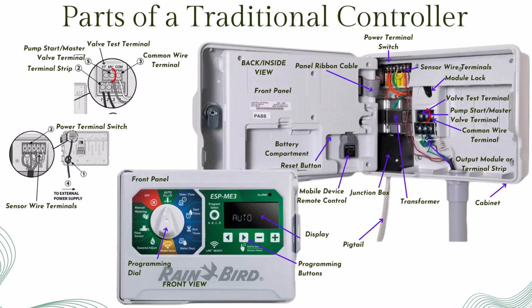The pump start or master valve terminal activates a pump or master valve whenever irrigation starts. Some controllers have a valve test terminal that gives constant low voltage power for troubleshooting valves. The common terminal is the shared return path for all your valve wires. The output module or terminal strip is where each zone wire connects. Modular controllers also have a module lock to keep those pieces in place.